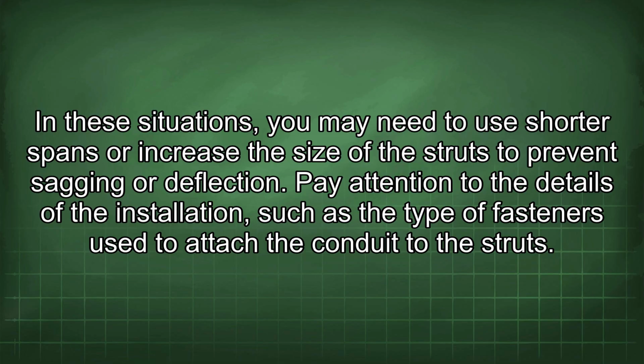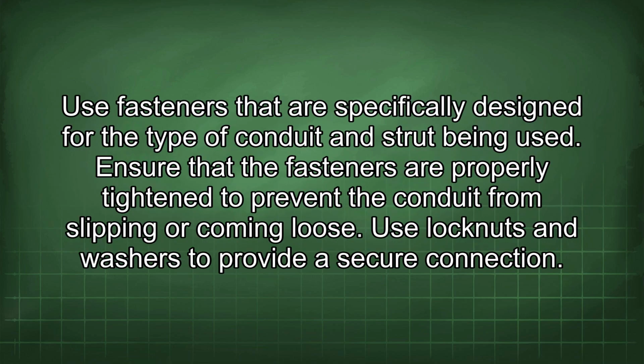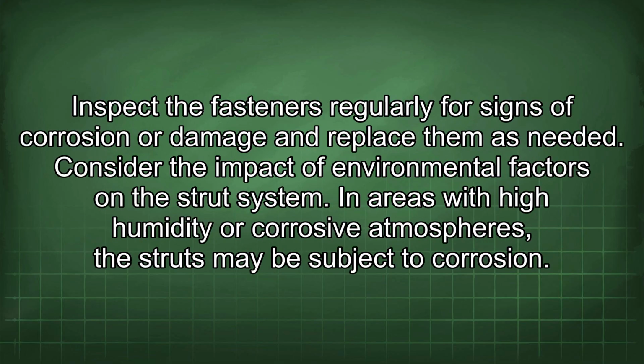Pay attention to the details of the installation, such as the type of fasteners used to attach the conduit to the struts. Use fasteners that are specifically designed for the type of conduit and strut being used. Ensure that the fasteners are properly tightened to prevent the conduit from slipping or coming loose. Use lock nuts and washers to provide a secure connection. Inspect the fasteners regularly for signs of corrosion or damage and replace them as needed.